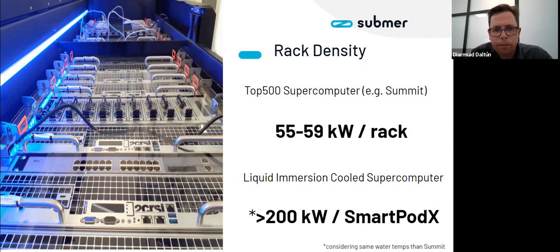We like to challenge that assumption, because it's a common discussion. As an example, Summit has a rack density of between 55 and 59 kilowatts per rack. The compute racks are much denser than the storage or networking racks, and that's on the higher end of the configuration for Summit. That's achieved through a combination of cooling technologies, obviously not just air.